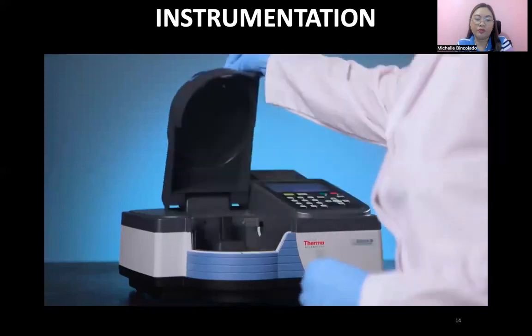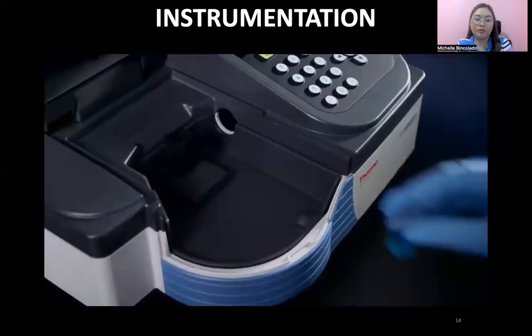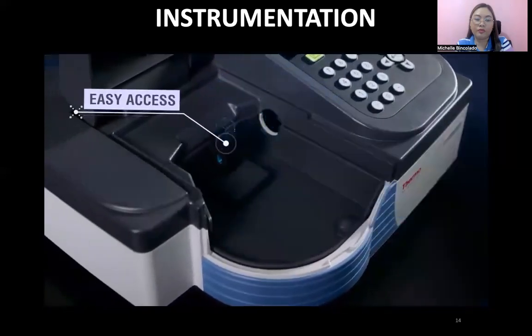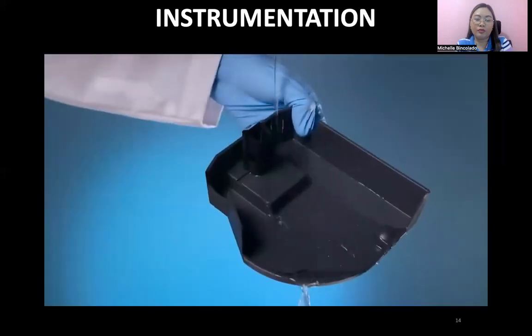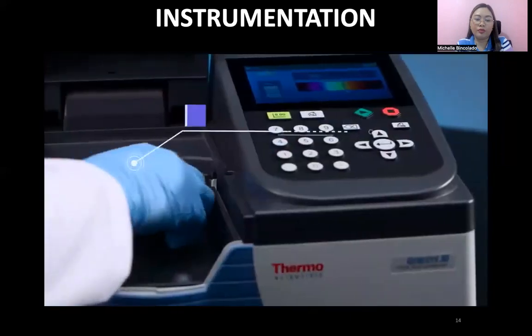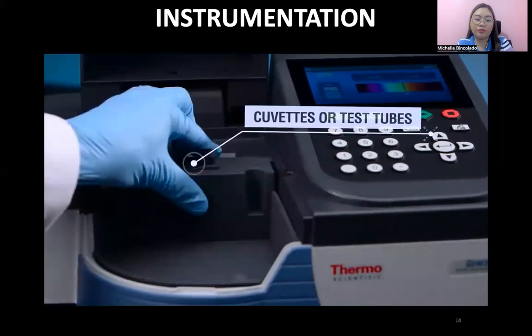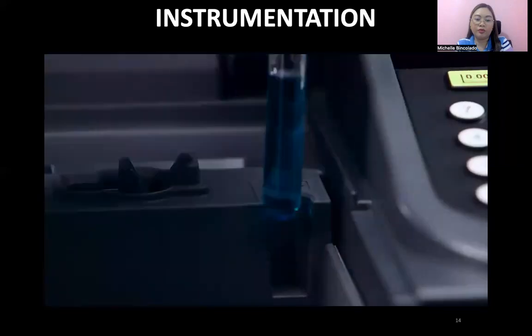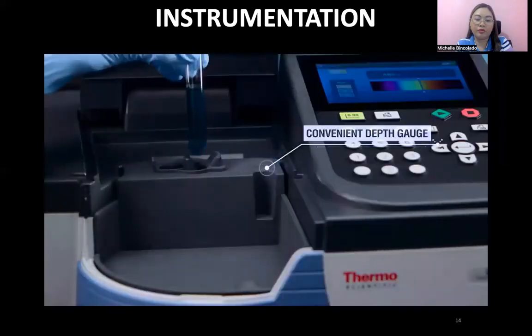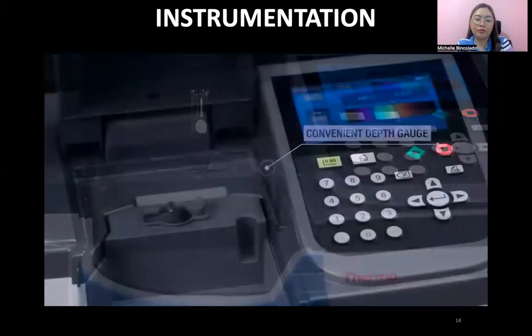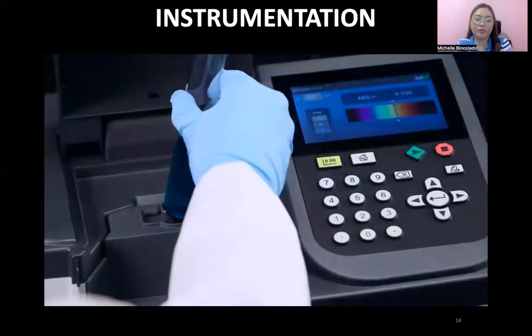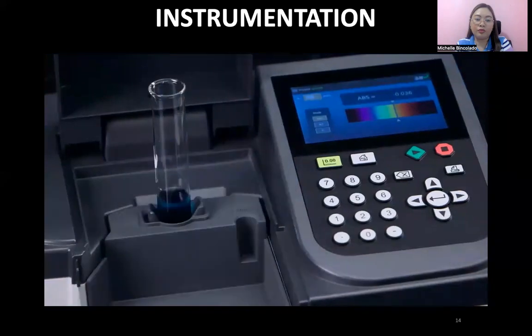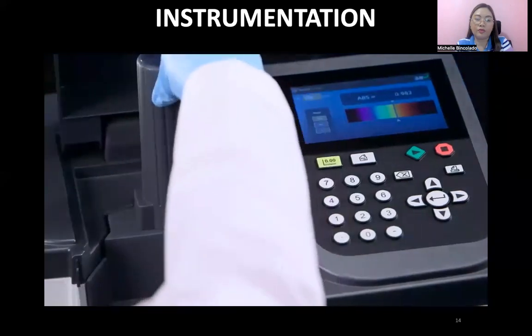Plus, it's designed for the way technicians actually work, with an oversized sample compartment that makes access easy and cleanup effortless. Use the Genesys 30 with cuvettes or test tubes. Our optional test tube holder includes a depth gauge for easy and accurate fluid measuring, and can handle test tubes up to 150 millimeters with an available tall test tube cover to ensure testing accuracy.